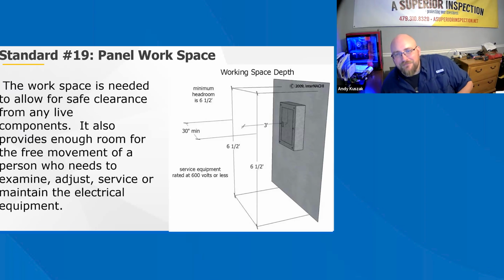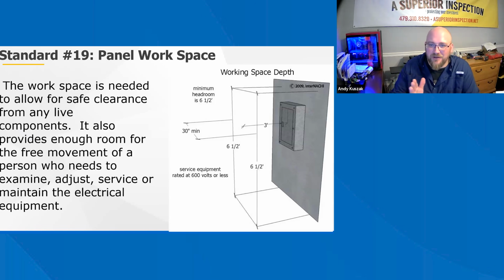If you've been an inspector longer than a week, you've probably seen people use the space in front of an electrical panel as storage, specifically for cleaning supplies. It's very common. Or if in a garage, see all the time where storage, shelving and stuff is placed either directly in front of or in front of the operable door, but where you can't take off the panel cover. So obviously we want to call all those things out and make sure that you have clear uninterrupted space to the electrical panel. Because homeowners don't understand the inherent dangers of an electrical panel.